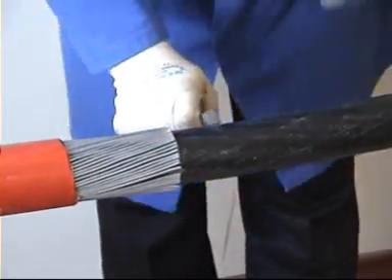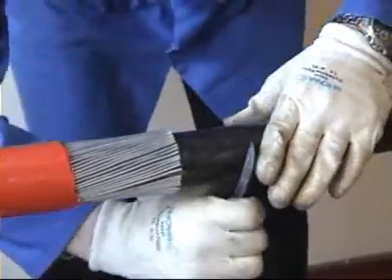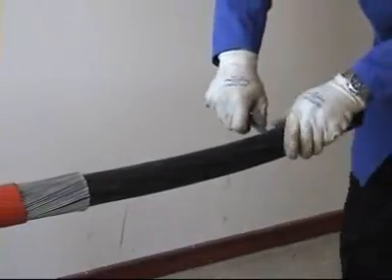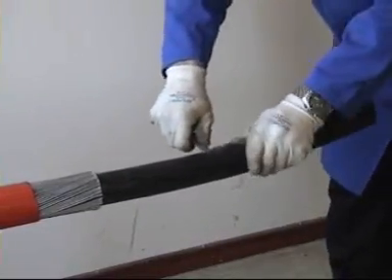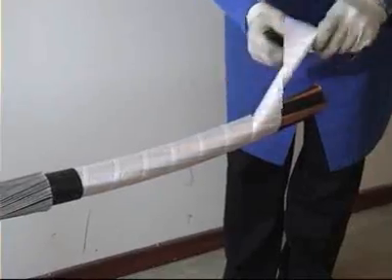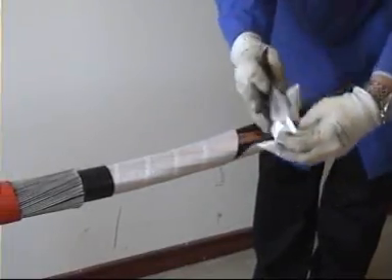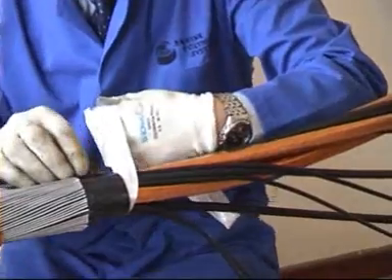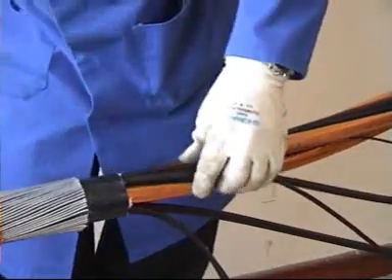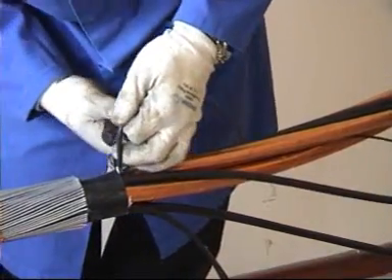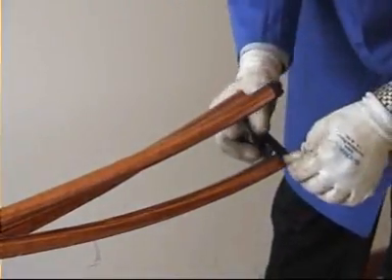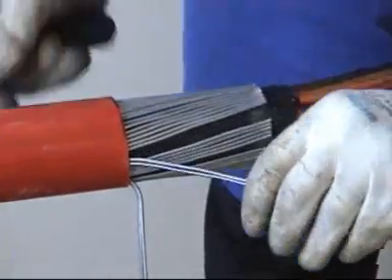Mark out the bedding. Put a radial cut on the sheath, being careful not to cut into the cores. Remove any filler tapes using a side cutter and a sharp knife. Just to keep the copper tapes in position, use some PVC tape at the end of the cores.